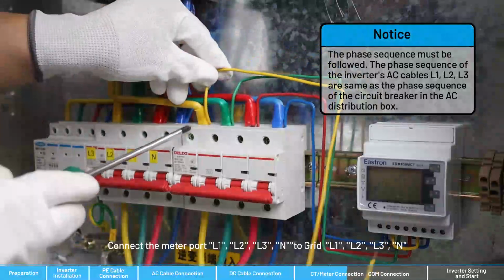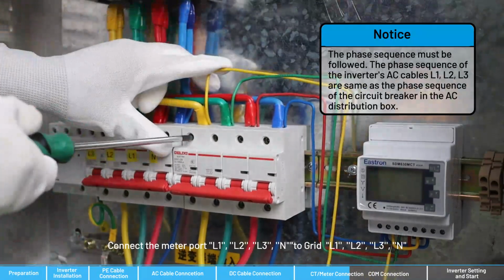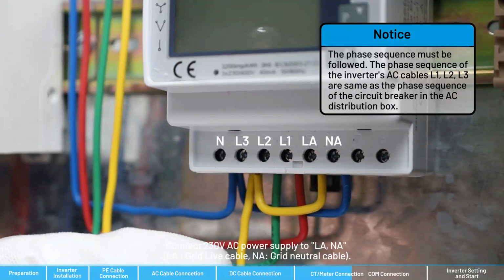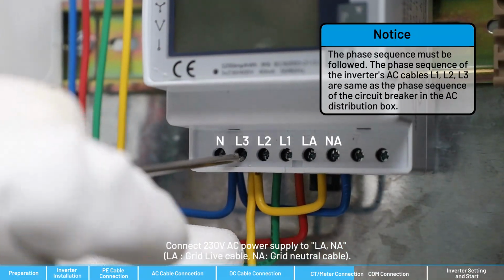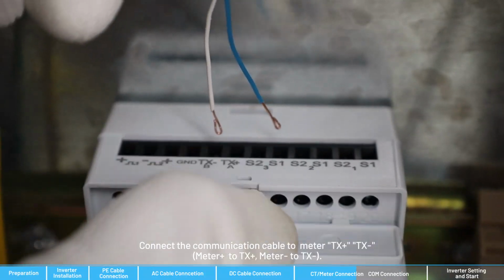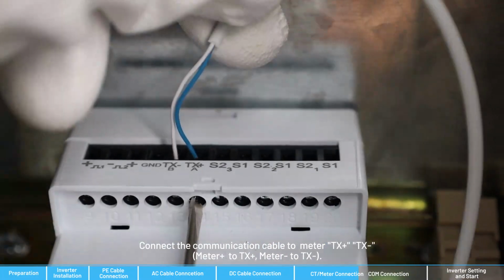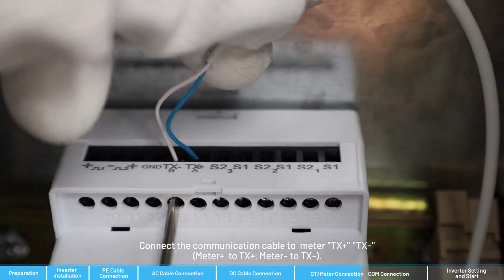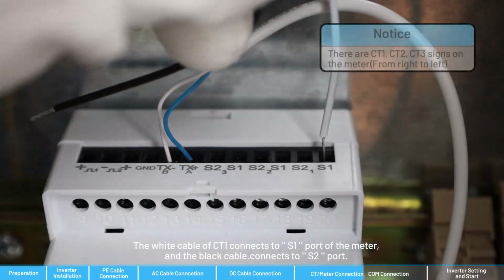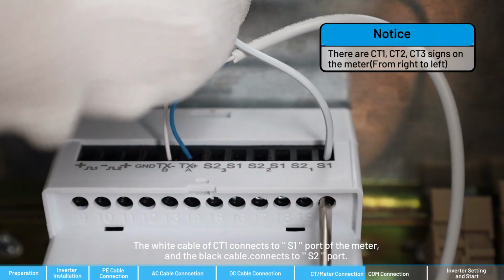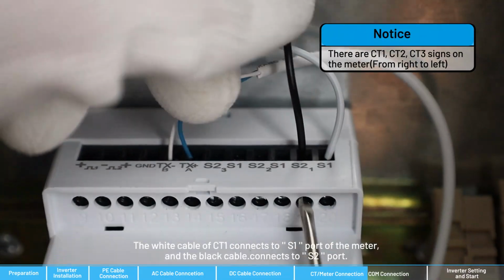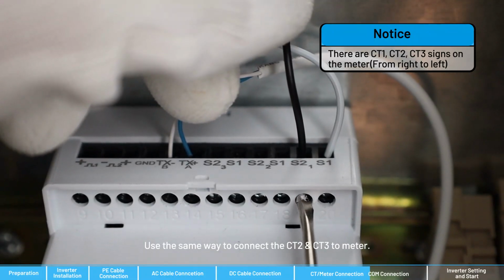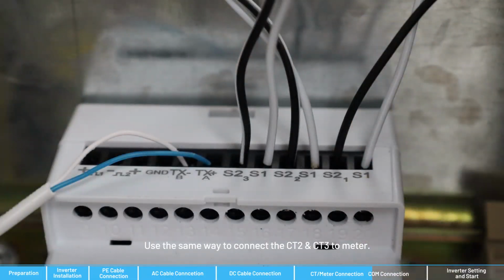Connect the meter port L1, L2, L3, N to grid L1, L2, L3, N. Connect 230 VAC power supply to LA and NA. Connect the communication cable to meter TX plus, TX minus. The white cable of CT1 connects to the S1 port of the meter, and the black cable connects to the S2 port. Use the same way to connect CT2 and CT3 to the meter.